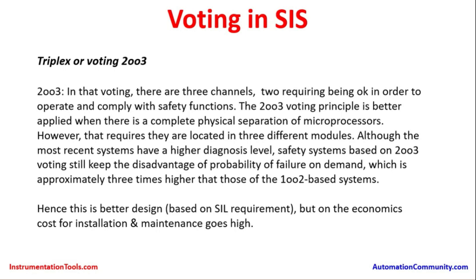It is better to go for triplex CPU-based PLCs — this is a triple modular redundant (TMR) architecture, with processors located in 3 different modules. Although the most recent systems have a higher diagnostic level, safety systems based on 2 out of 3 voting still have the disadvantage that the probability of failure on demand is approximately 3 times higher than those of a 1 out of 2 based system. That is why 2 out of 3 requires detailed engineering to implement properly.